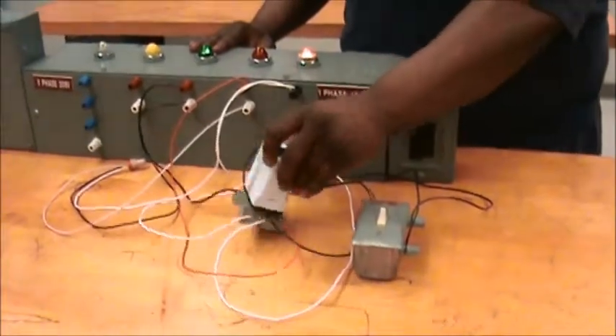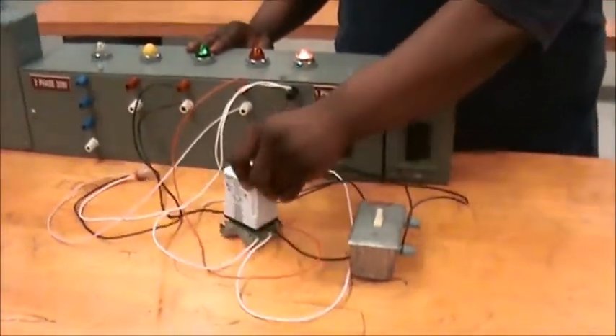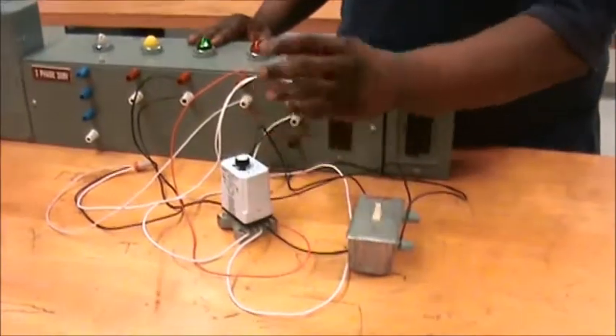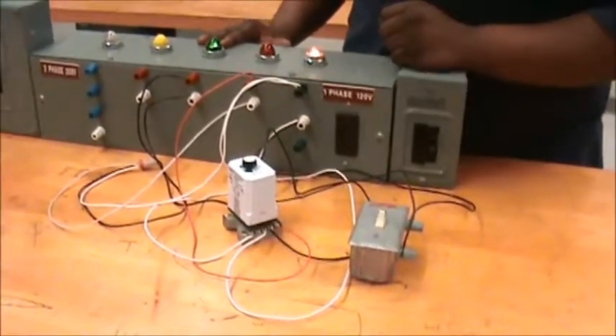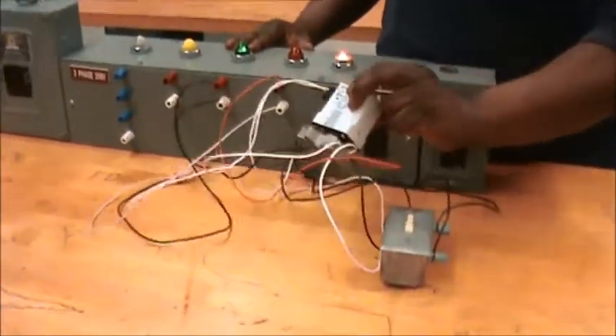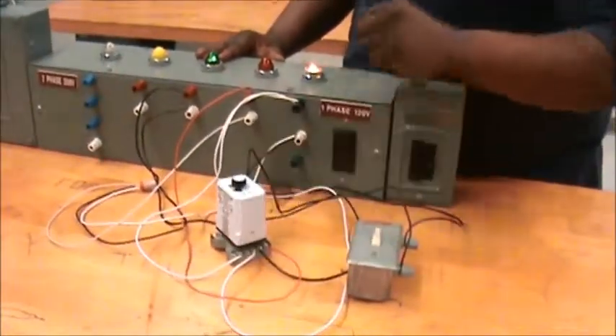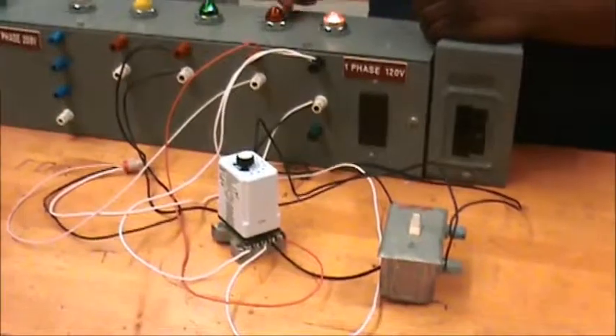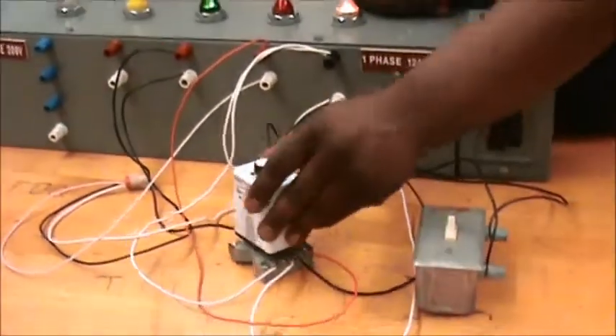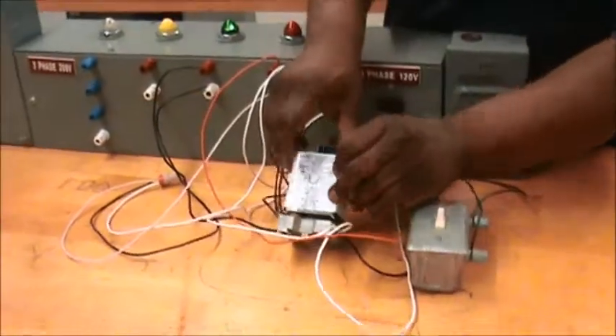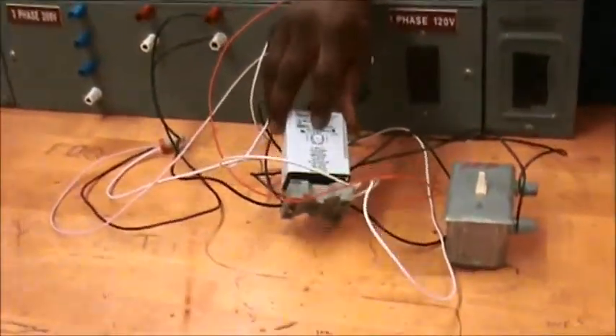One other thing about the off-delay timer is that the off-delay timer has to be wired hot all the time. If you do not wire the off-delay timer hot all the time, then you'll never have the power to make the contacts change their state. The off-delay timer actually contains a contact.